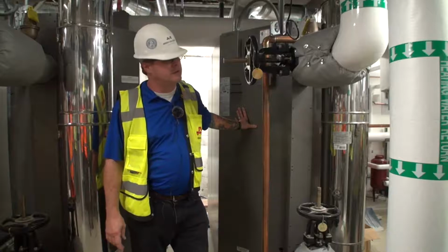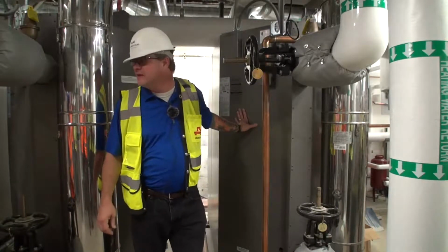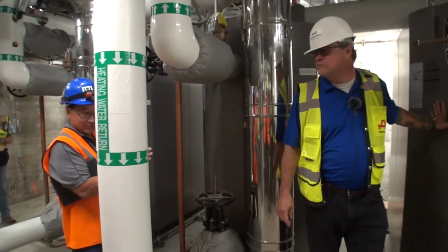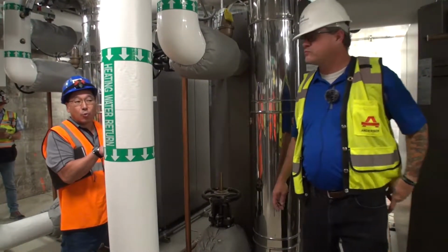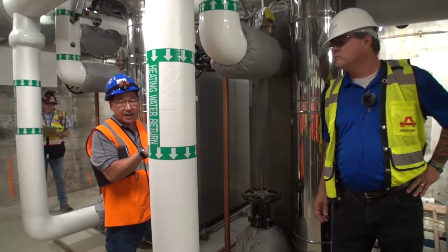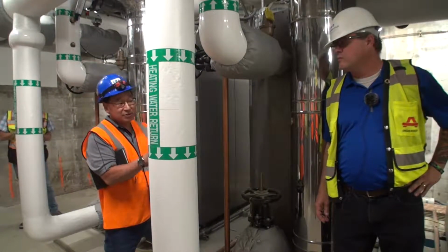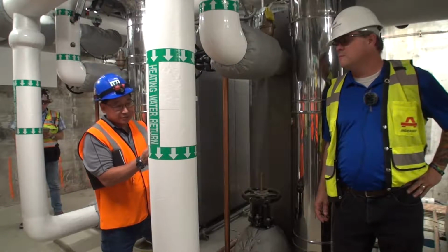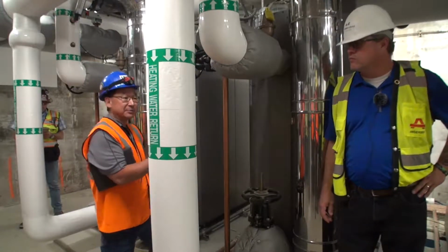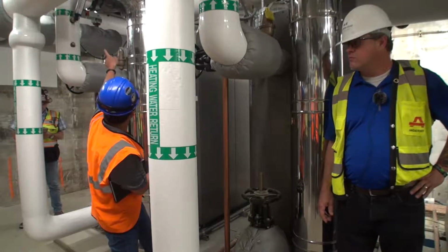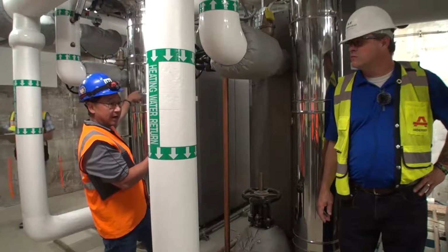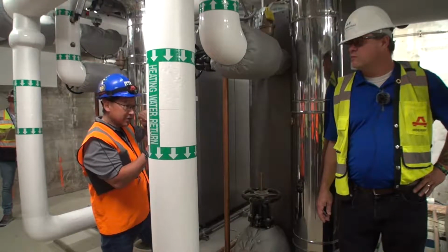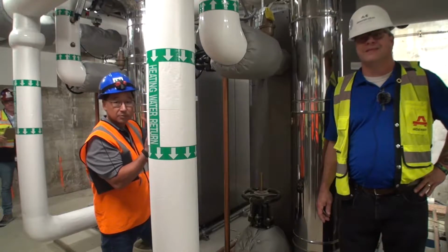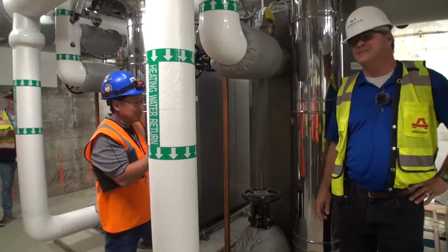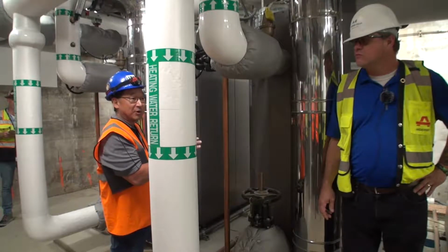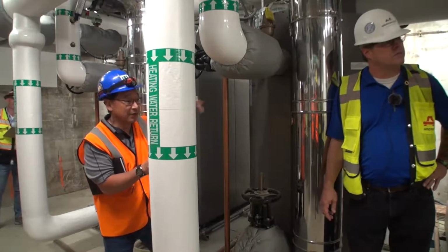That's a school in Northeast Portland? Yeah. I can't remember. Okay, so what happened in that case, since we're going off on that, is that you have 2 boilers. One actually was turned off, and something happened. How these valves work is, as Dustin mentioned, the last boiler fired keeps its valve open. If you look at this one, the window's yellow, so water's flowing through this boiler now. When there's a demand for heat, the boilers will look at it and decide which one to fire. If it's this one, this one will open and this one will close.